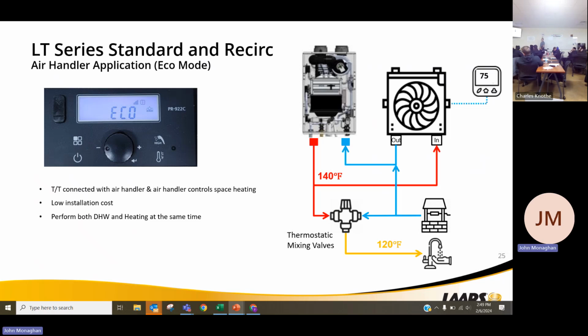But you can run it connected to an air handler. It's not exactly designed for space heat, but it can work. Like you can run an air handler, you do space heating off of a tanked water heater. Yeah. The thing that's got the thermostatic mixing valve, because when it comes on, when someone's in the shower, suddenly they find themselves in a cold shower. Yep. 20-degree water coming through.